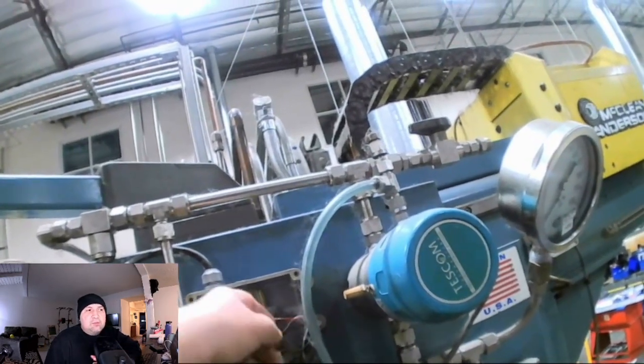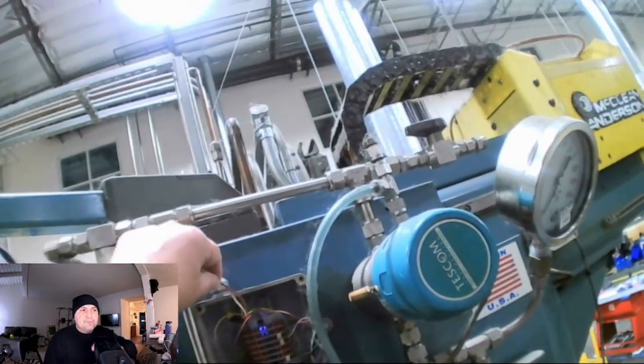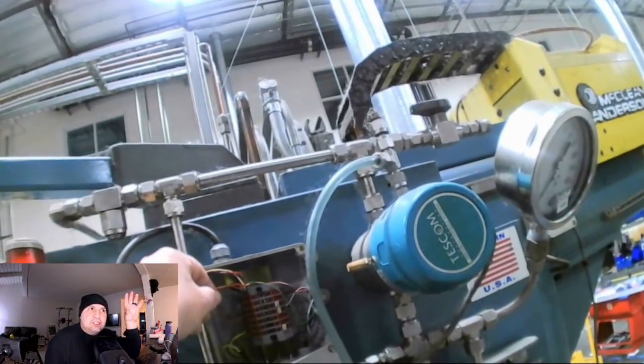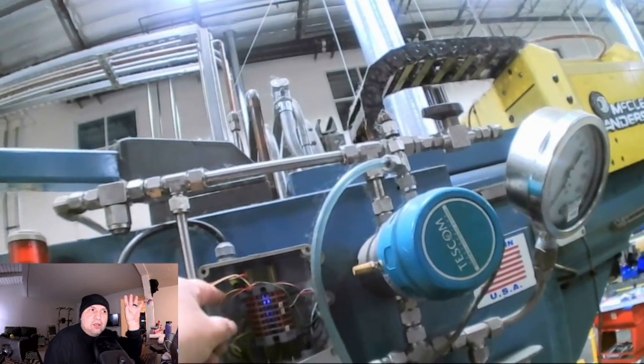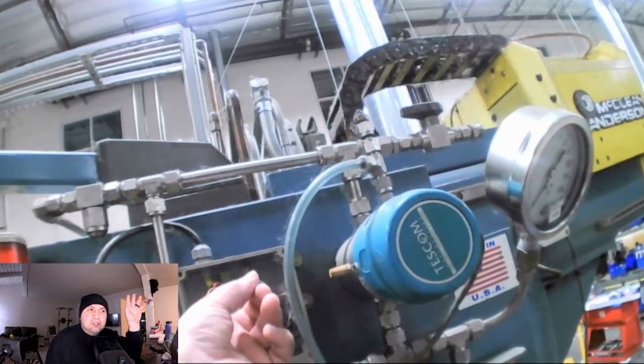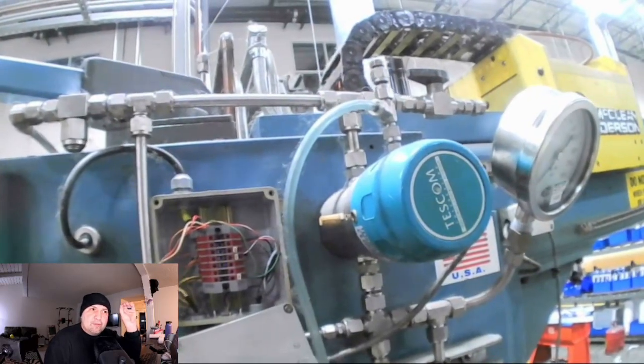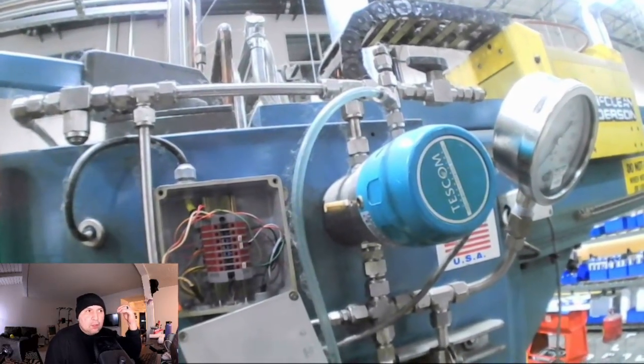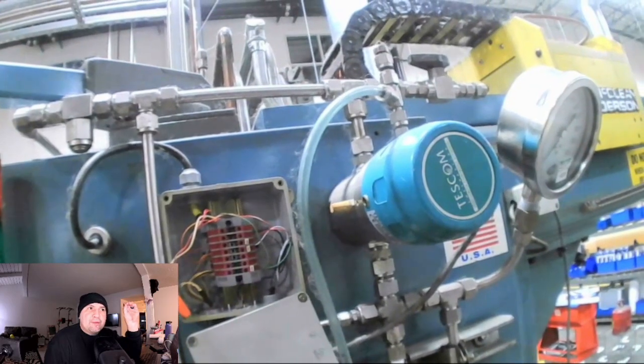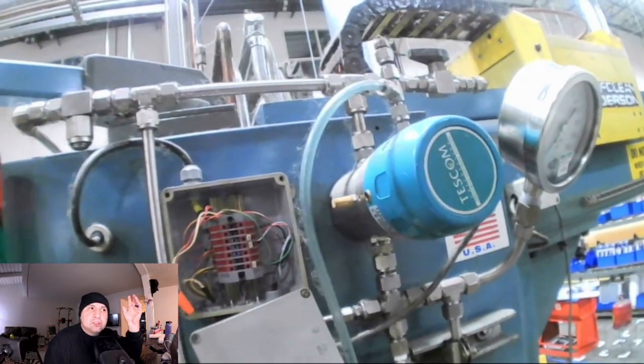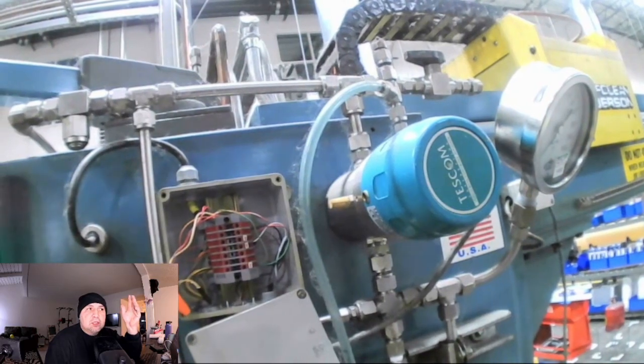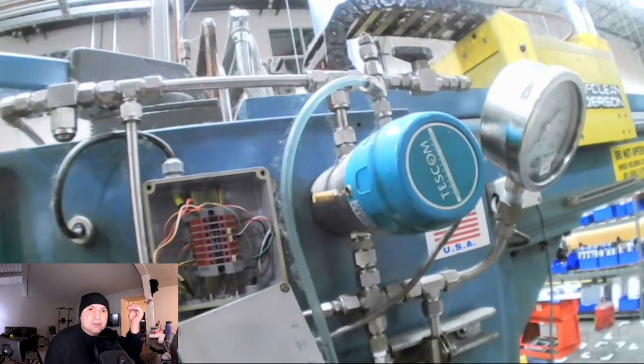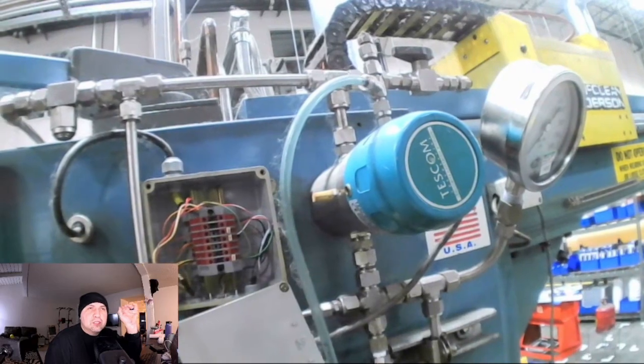There's a lot of low voltage communication going on here. This unit uses a lot of milliamp signals to communicate with the machine, and it's also communicating with the Windows computer system of this machine, sending signals to the communication board so you can see the pressures in real time on the computer screen for their process.